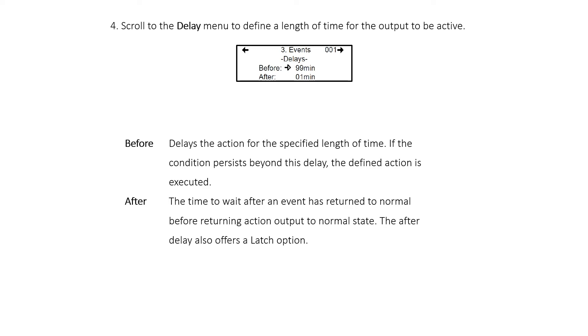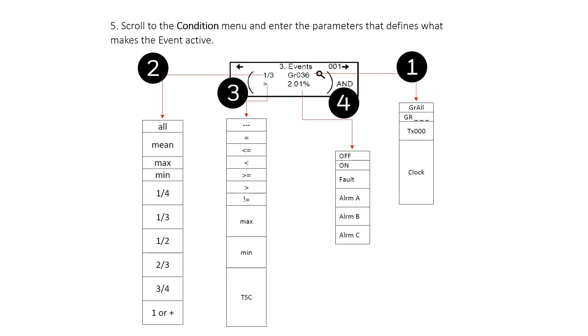The After Delay also offers a latch option. Scroll to the Condition menu and enter the parameters that define what makes the event active. Define the transmitter or group of transmitters included on this condition, how many of these transmitters should meet the condition to trigger the event, when the set points will meet the condition, and the set point to meet the condition on number 3.